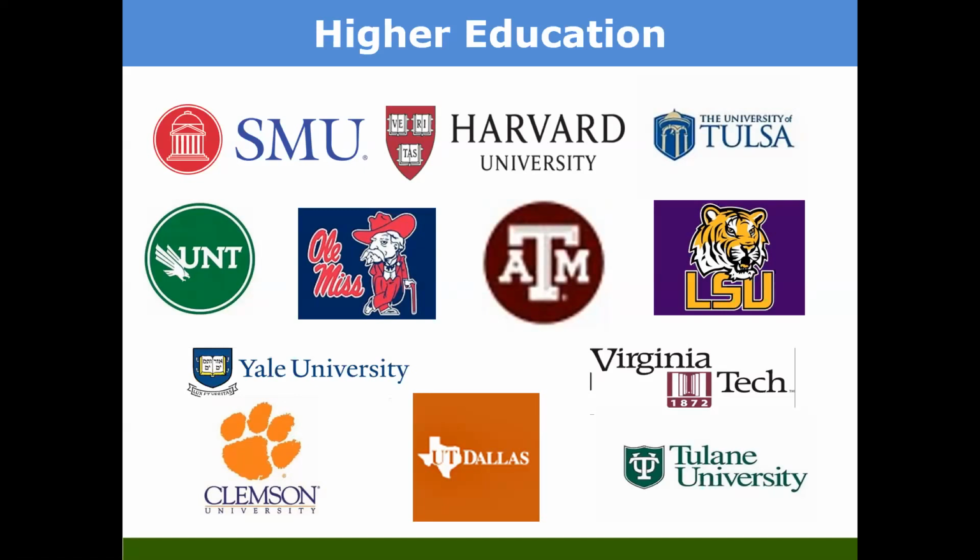We did their veterinarian school. We also did their new indoor football practice field. And we just mentioned ASHRAE 62.1. If you use the normal ventilation rate procedure, they had to bring in 24,800 CFM of outside air. And even though it's a large space, there were only 200 people, maximum occupancy. And by using the indoor air quality procedure, you could technically lower that to 1,000. But because of pressurization with their exhaust fans and lockers, they ended up putting in right at 12,000, but less than half of what they would have brought in.